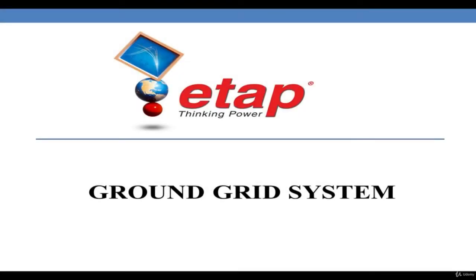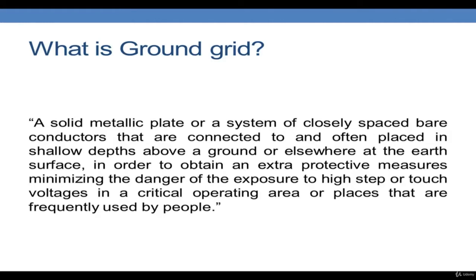In this section we will study more about ground grid systems or earth mat systems. So let us see what is the definition of an earth mat or a ground grid. According to IEEE, a solid metallic plate or a system of closely spaced bare conductors that are connected to and often placed in shallow depths above a ground or elsewhere at the earth's surface in order to obtain an extra protective measure minimizing the danger of the exposure to high step or touch voltages in a critical operating area or places that are frequently used by people. So this is the IEEE definition for what an earth mat or a ground grid is.